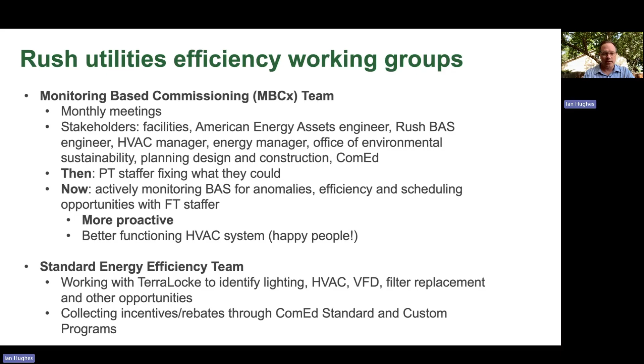All right, so from a really high level, there may be some folks who are wondering what the heck this acronym MBCx is. Monitoring-based commissioning is effectively just an analytical approach of using our building automation systems, pulling data from them to understand where we have low capital, high ROI opportunities for energy efficiency. It's estimated this could be between 4 and 10% of total annual energy usage. Most of those initiatives typically fall in the free to $5,000 range for cost upfront. So it's really, really low cost.